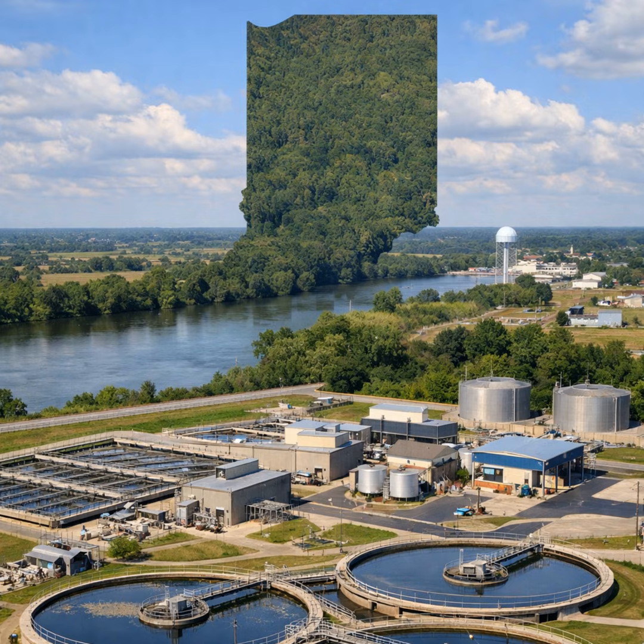Surface loading. One of the guidelines for the design of settling tanks and clarifiers in treatment plants, used by operators to determine if tanks and clarifiers are hydraulically over or underloaded. You can also compare this to an overflow rate, the definition of overflow rate. To calculate surface loading: surface loading in gallons per day per square foot is equal to flow in gallons per day, divided by the surface area in square feet. And that will give you your surface loading.